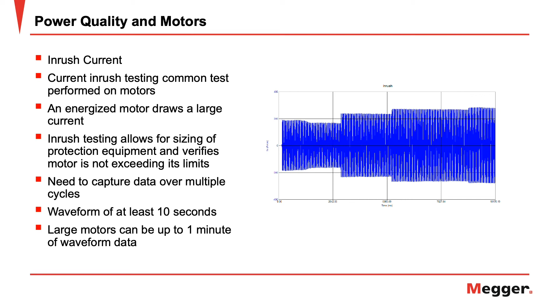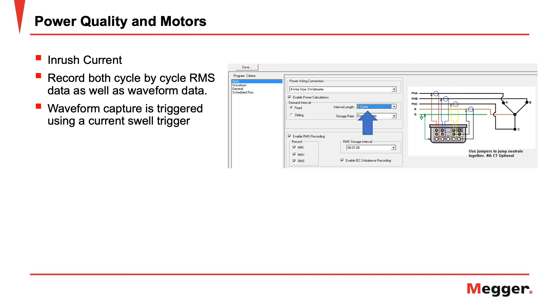To perform inrush testing, it is recommended to record both RMS data as well as waveform data. And that RMS data should be recorded every cycle. A waveform capture will be triggered using a current swell trigger that's set approximately at 1 to 2 amps.